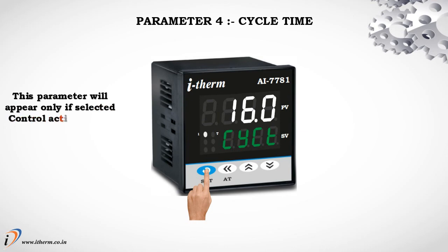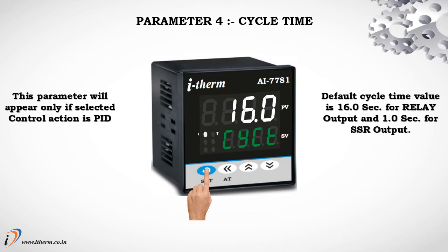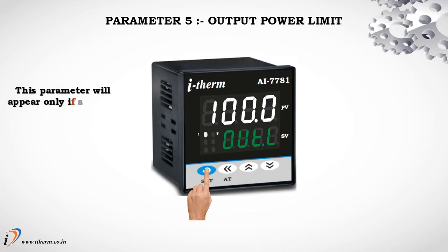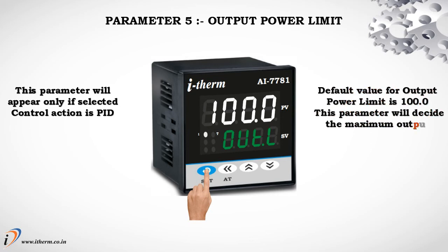Parameter 4 is Cycle Time. This parameter will appear only if the selected control action is PID. The default cycle time value is 16.0 seconds for relay output and 1.0 second for SSR output. Parameter 5 is Output Power Limit, which also appears only in PID mode. The default value is 100. This parameter decides the maximum output power in percent applied to the load.